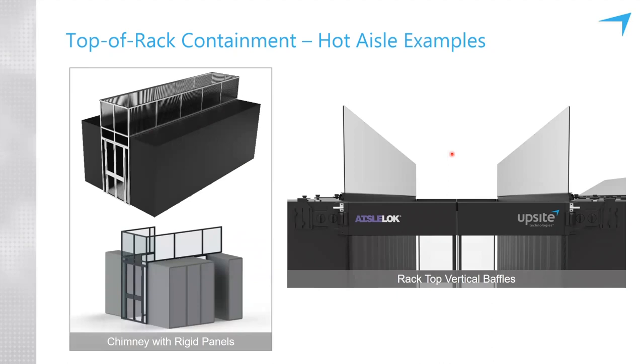Here's a few examples of hot aisle containment. These generally look like chimneys. In this case, ducted. What we're not seeing is the ceiling. These could be ducted all the way to the ceiling, or they might be a partial chimney just to contain the air and direct it towards the ceiling return. Down here, we have an example of a very short cabinet with some challenges of open spaces, and there's an L-shaped jog in the wall here, so the containment has different length chimneys on either side.